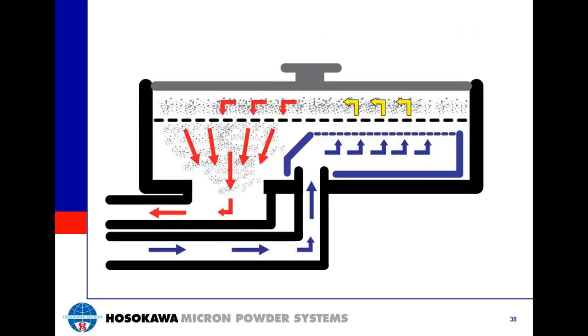The Hosokawa Micron Air Jet Sieve model MAJS-X is a highly accurate and reliable particle size analyzer, used primarily for analyzing dry powders between 4,750 microns to 5 microns by means of the pneumatic sieving principle. As displayed on screen, the pneumatic sieving principle uses a positive airflow introduced upward through a rotating wand located beneath the sieve screen. As the wand rotates, it disperses and distributes the material across the sieve screen, achieving 100% coverage.